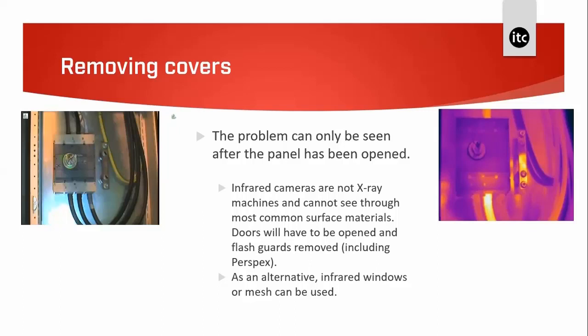You may encounter situations where the previous thermographer carried out a survey without opening any covers — it's difficult to convince the end user to open covers if they've experienced this before. An alternative to opening covers is using infrared windows. However, check with the switchgear manufacturer before retrofitting them, to ensure the windows are correct for the installation and do not invalidate the equipment certificates.